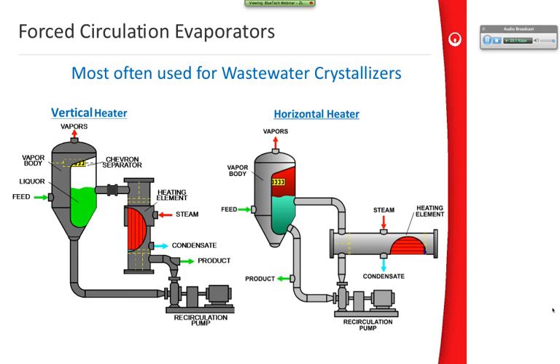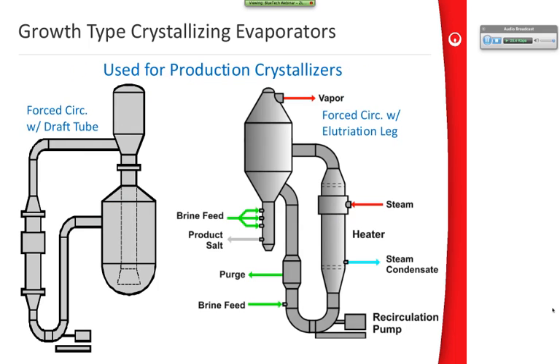The heat exchanger can be oriented either vertically or horizontally. You'll notice, though, that the heat exchanger is located below the level of liquid in the vapor body, so that the heat exchanger is flooded in a forced circulation type unit. No evaporation occurs inside this heat exchanger. It's just sensible heat that's transferred. All the evaporation occurs as a flash in the vapor body.